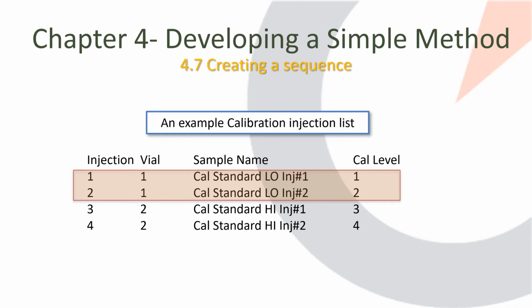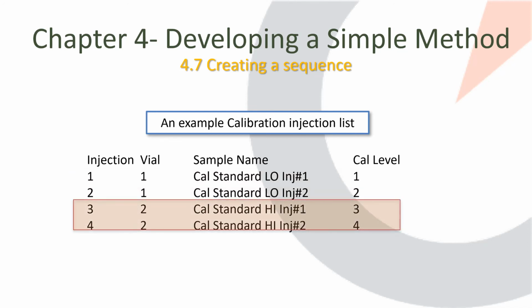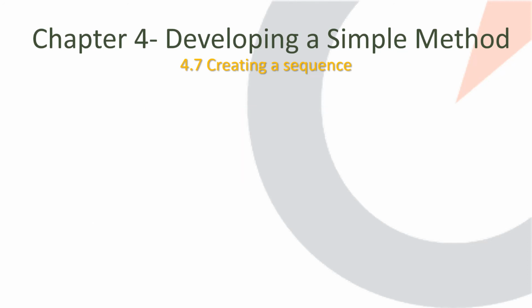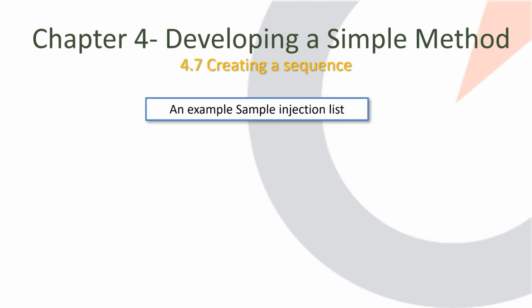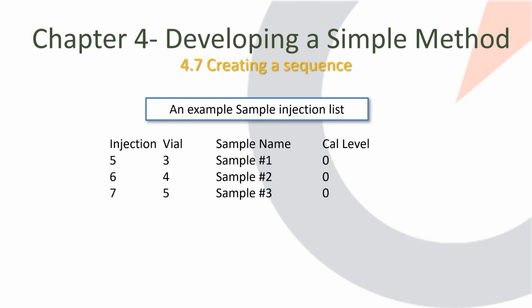We don't consider channels in the calibration injection list. If your instrument supports multiple channels, then you will have multiple calibration files, which must conform to one another in terms of standards, replicates, and levels. After the calibration injections, we will run 3 samples. These are to be analyzed according to the newly updated calibration file. These analytical runs do not involve an update, so the calibration level is 0.